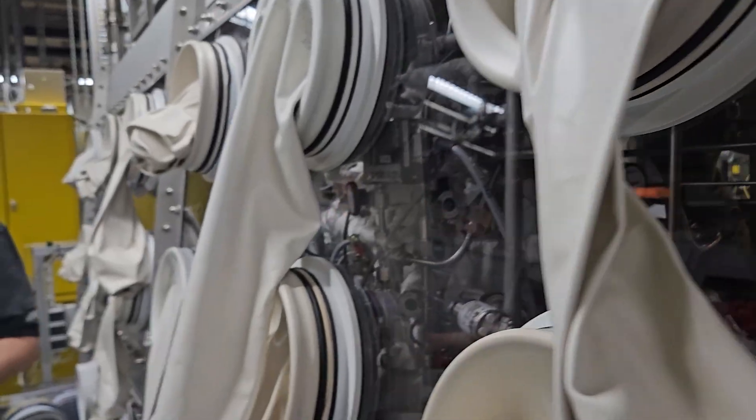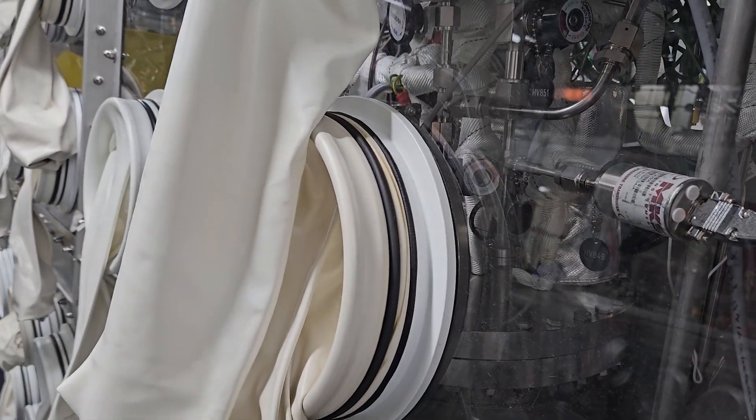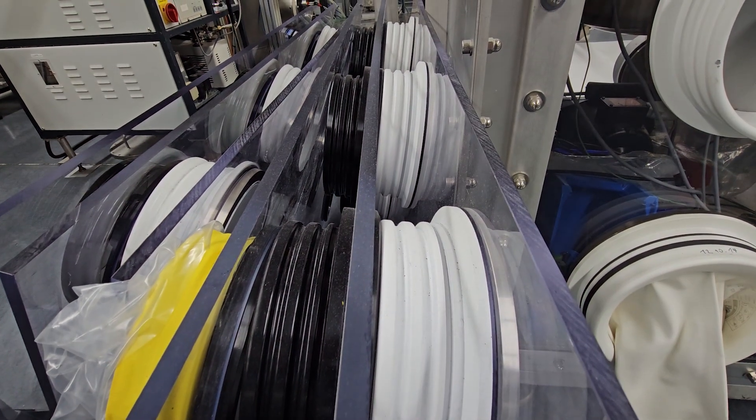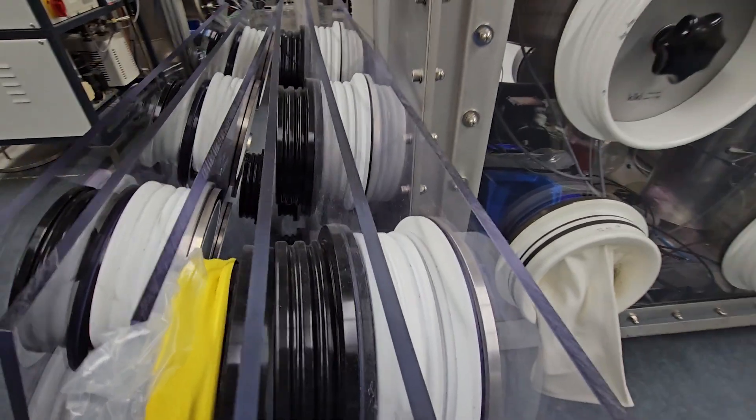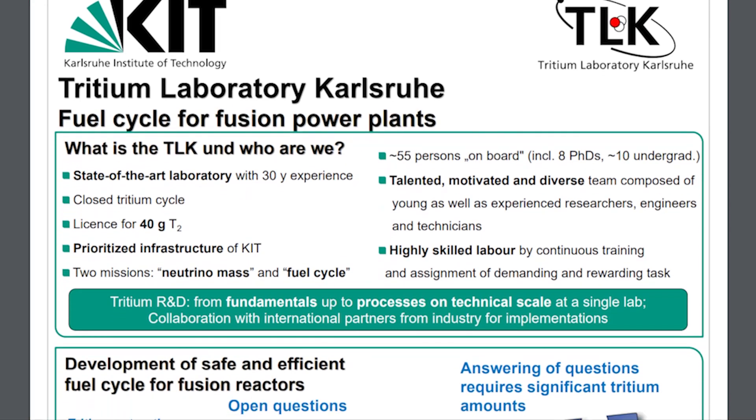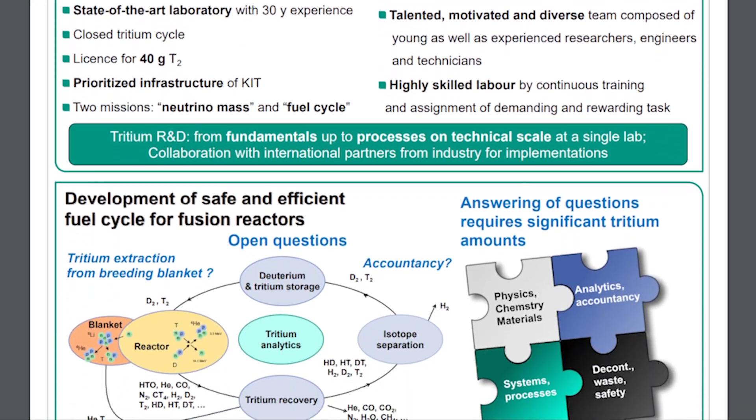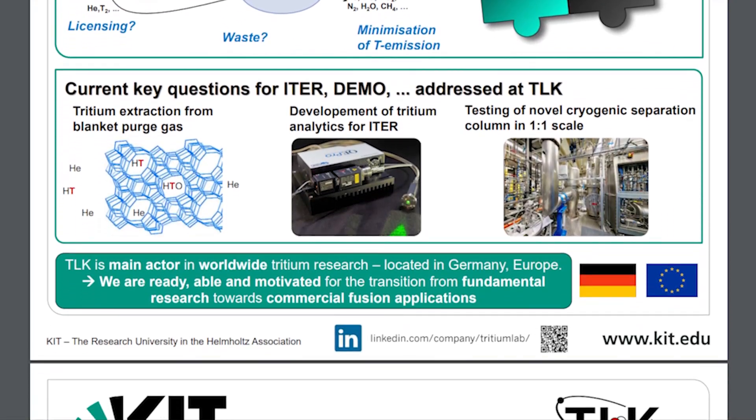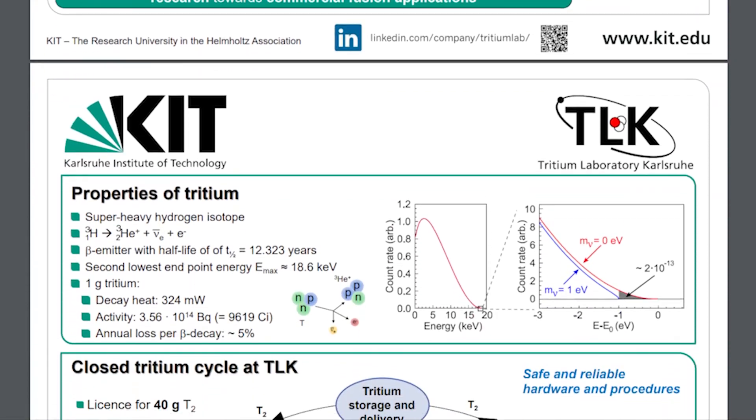For working with non-radioactive hydrogen isotopes, gloves do not have to be clean or anything like that. Only when working with tritium, but it should be in the tubes anyways. Gloves are sealed from the inside when not in use, as the rubber of the gloves otherwise easily damages. Now, tritium is used in such experiments. And then, 12 years half-life, that will not have completely decayed after the experiment, but it's still radioactive and expensive. The losses due to radioactive decay are about 5% per year. It would only make sense to recycle the rest. Blowing it out and buying new is just not an option.